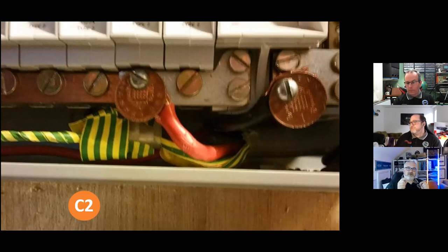Yeah, because again, if we look at the definitions, C2 is potentially dangerous, urgent remedial action required. There's no definition or guidance on what the remedial action is, or what timeline you put to urgent remedial action. In C1, it's immediate remedial action required, and my brain would want to fix that there and then, which would ruin my day. And that's why Phil's used C1, and I get that.